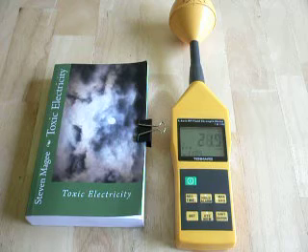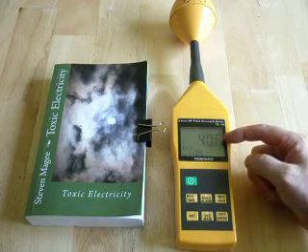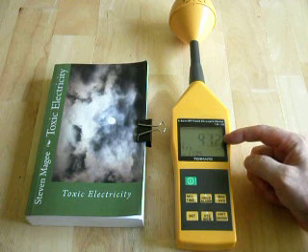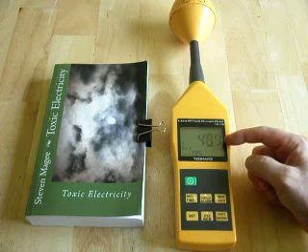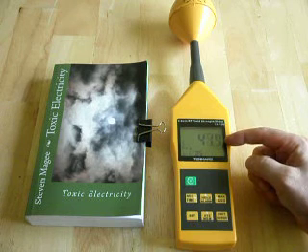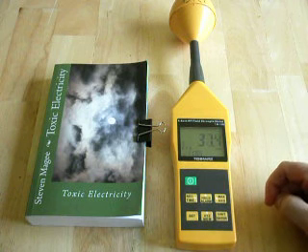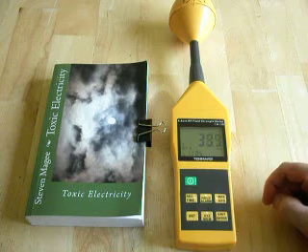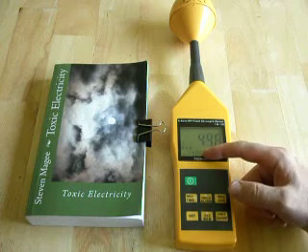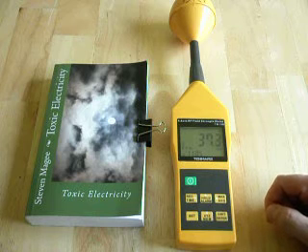So let's go through the features of the meter. Right now we're reading millivolts per meter, and we're getting in the region of about 38 millivolts per meter on the instantaneous reading setting. Over here we have a bar graph that records the instantaneous value in real time, and down here we have a clock.